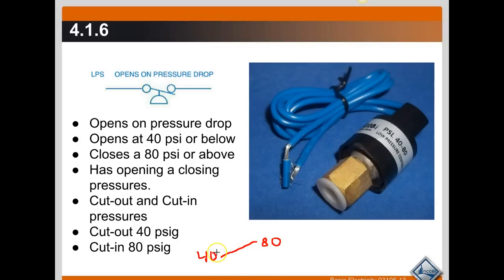So as it rises from its cut-out pressure to the cut-in pressure, there's a dead band here of 40 psi G. And the same thing when it's at 80 and begins to fall, the system will continue to run. It doesn't cut out until it hits 40, so there's that 40 psi G dead band as it rises and falls to the cut-in and cut-out pressures.